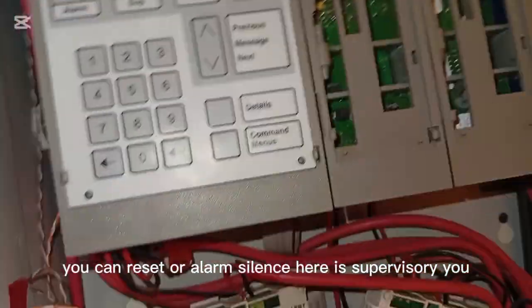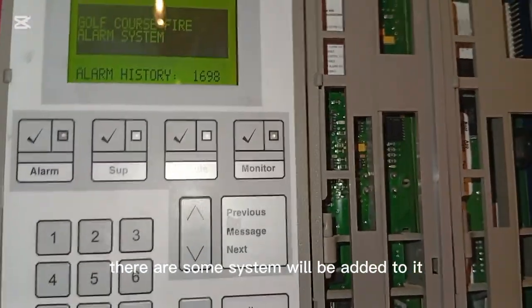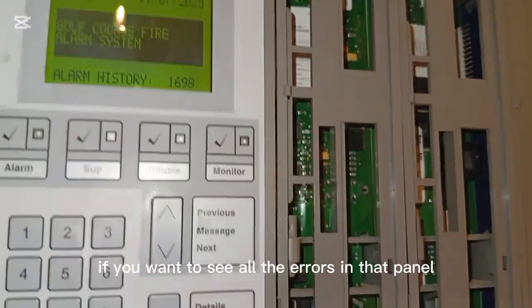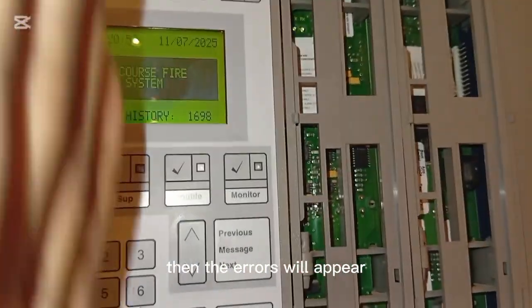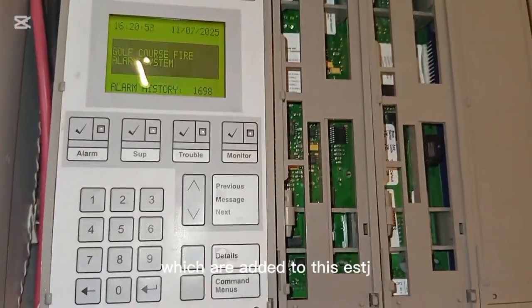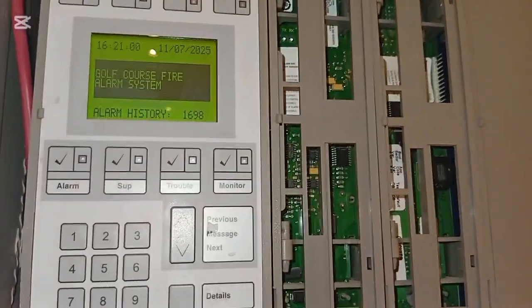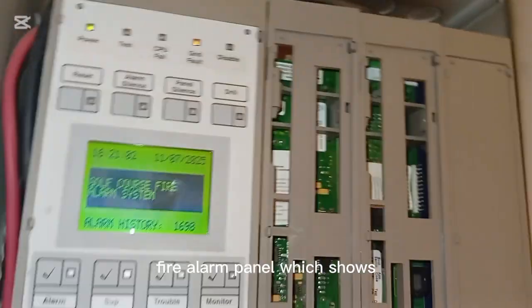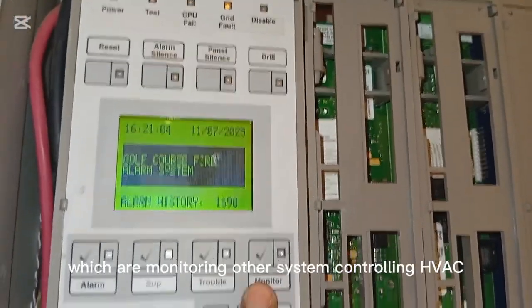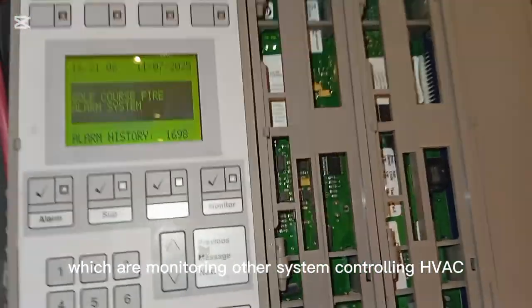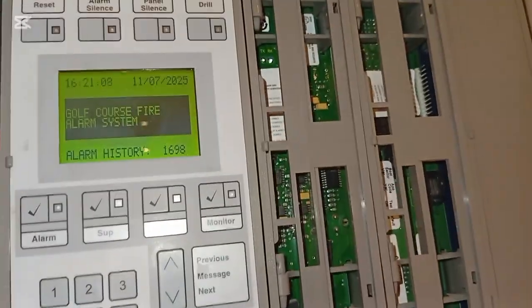Here is the supervisory. Some systems will be added to it. Then here, the trouble button: if you want to see all the errors in that panel, you press this button, then the errors will appear and bring you to the errors column. Then we have monitoring. We have other systems added to this EST3 fire alarm panel, which monitor other systems, controlling HVAC, controlling lift, controlling water flow switch, and so on.